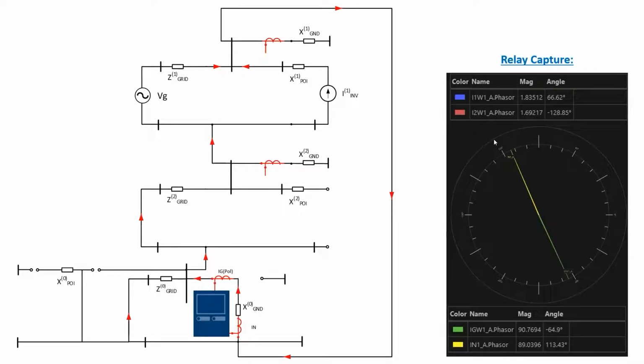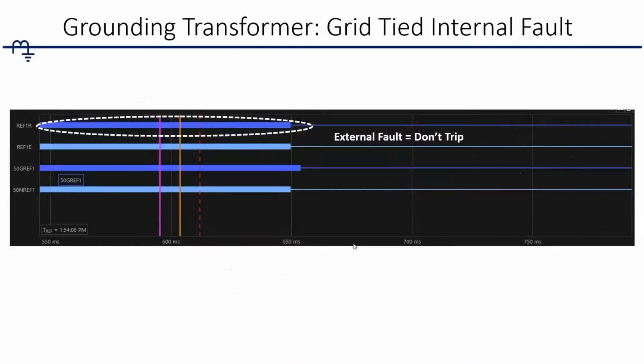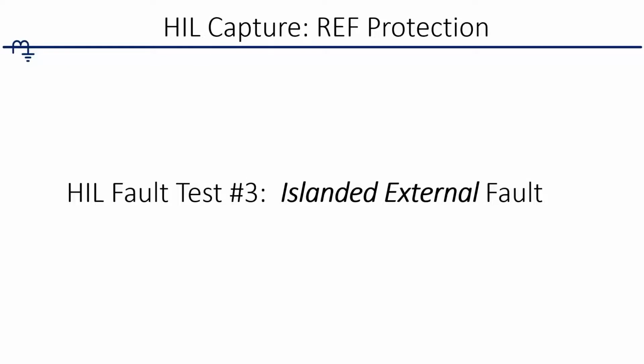So here's the measurement, and you can see it's almost exactly 180 degrees, which was good. That's kind of what we were expecting. And I went through and drew these out again, and as you can see, not much of a surprise there. The reason for that is when zero sequence flows through this network, it comes into the polarity side of the CT and then is injected at the top in the non-polarity side. So that's the reason you're getting that wide angle there. And I'll show you, this is a reverse. We said forward was internal, reverse is external. So it was an external fault, so the relay blocked. It did not operate for this, which is good. That's exactly what we wanted to see. Customer was happy with that. That's exactly what we wanted.